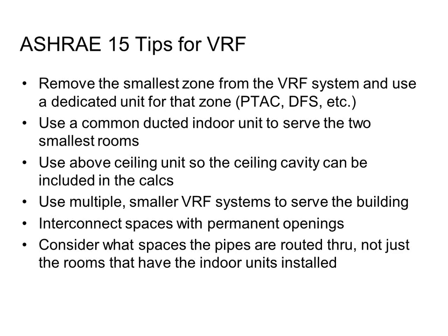Ron's asking what type of refrigerant piping can be used, hard K or ACR, annealed soft K or ACR copper. I'm going to go with the manufacturer's recommendation for the answer on that, Ron. Most times what they want to see is soft lines, continuous. They'd really like you to take out 100-foot line sets and roll them out and use that. So they really want you to go the ACR route. They will allow you to use hard pipe. Most manufacturers will, but then they start changing the rules and the maximum distance that you can go.